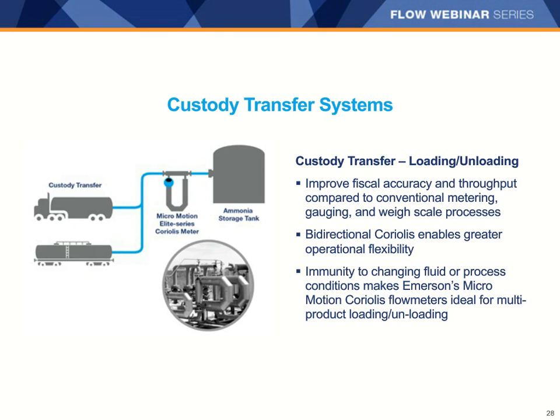Micro Motion Coriolis meters are uniquely situated to act as pay and check meters in your ammonia receiving area. By measuring direct mass flow, they verify the amount purchased as well as the received concentration. They're an excellent insurance policy to assure that you get what you are paying for from your ammonia suppliers.